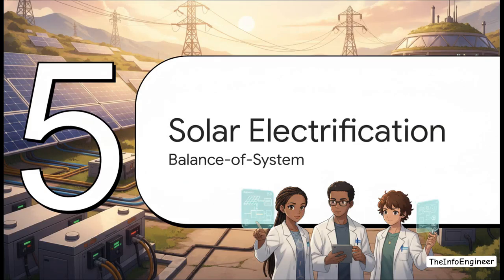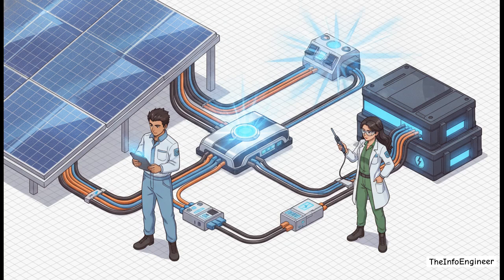Section 5. Solar Site Electrification and Balance of System Engineering. A solid off-grid solar setup is so much more than just slapping panels on a roof. It requires meticulous balance of system, or BOS engineering. Sure, you have your PV panels and your battery bank, but you must integrate a charge controller to manage the flow. You need proper fuses and breakers to hit NEC overcurrent protection standards.